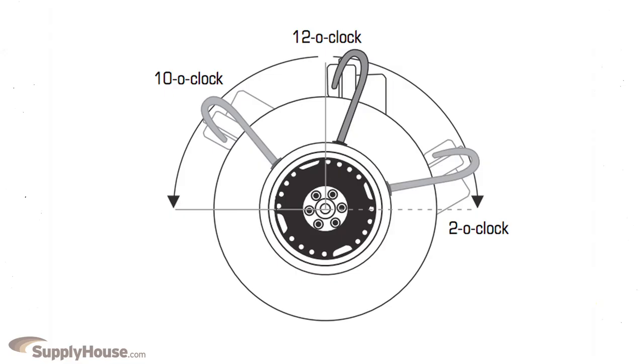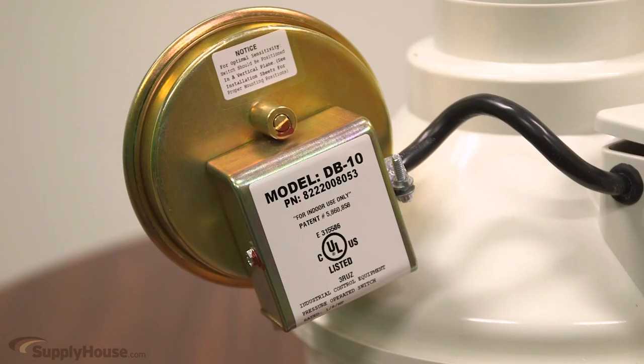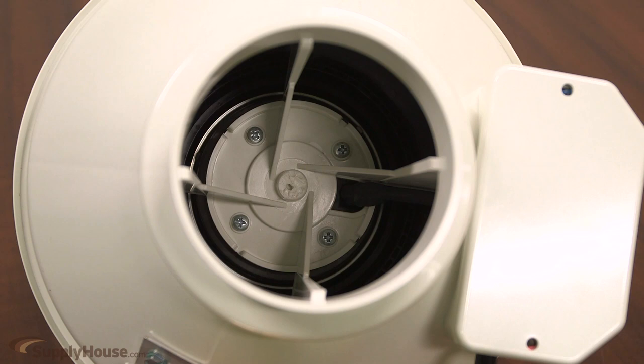The motor bearings are permanently sealed self-lubricating ball type. This Fantech dryer booster fan is engineered of thermoplastic resin and features an integrated automatic pressure switch. The fan's backward inclined blades allow lint to pass through the fan, and this unit has a self-cleaning backward curved impeller.